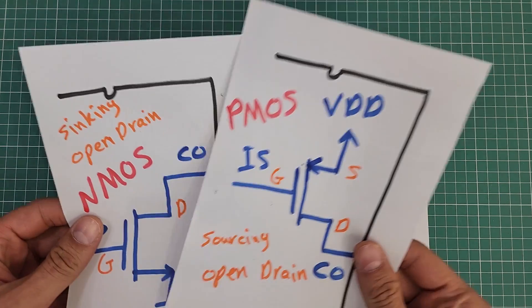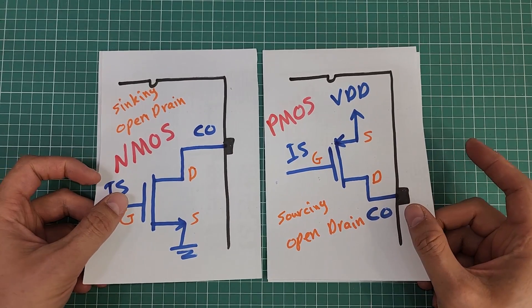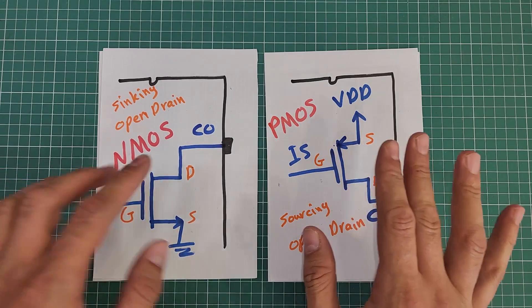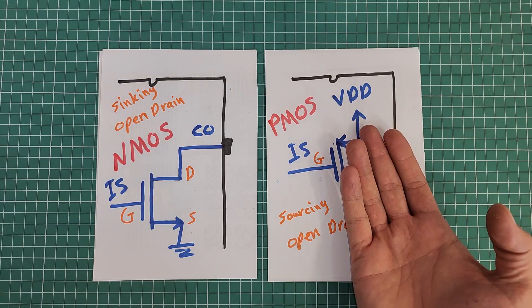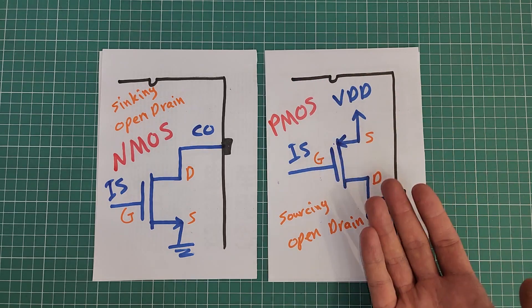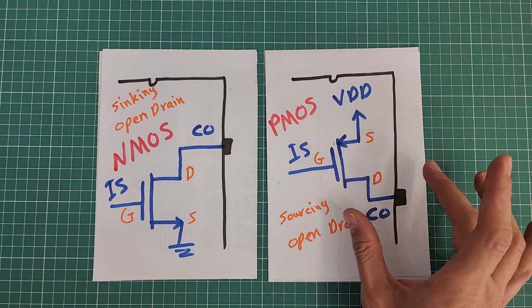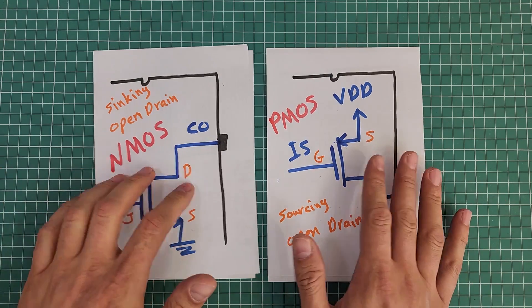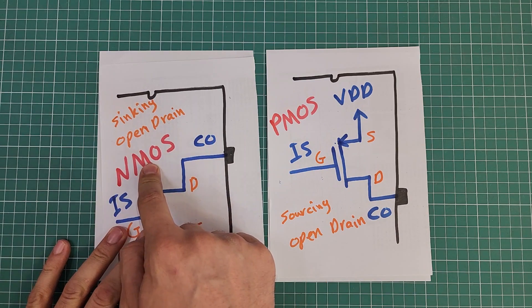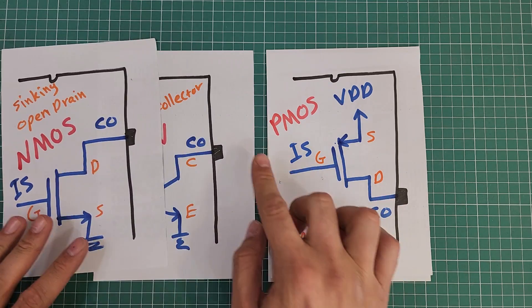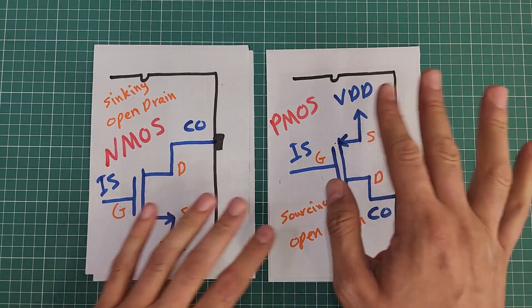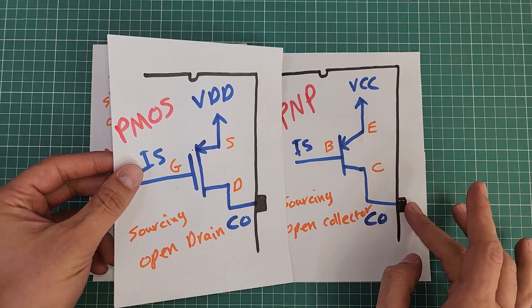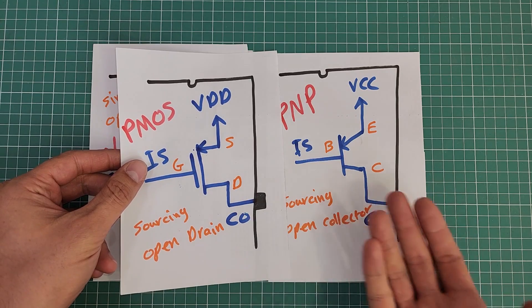There is a similar situation with open drain outputs. Open drain outputs can be made using NMOS transistors or PMOS transistors. Similarly, NMOS open drains are more common. By looking at these diagrams, you can see that PMOS open drains connect the output to VDD — the source voltage — when active and leave the output in the air when inactive. In this video we will ignore PMOS open drains because they are rarely used. NPN type open collectors and NMOS open drains are called sinking type outputs because they connect the output to ground when active. PNP type open collectors and PMOS open drains are called sourcing type outputs because they connect the output to source voltage when active.